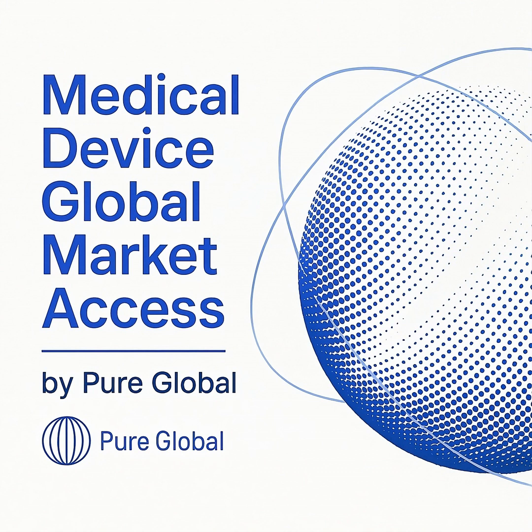For all devices, excluding the very lowest risk Class A non-measuring and non-sterile products, you must apply for an import license using Form MD-14. This application is submitted through the CDSCO's online portal and must be supported by two crucial dossiers: a device master file, or DMF, for each specific device or device family, and a plant master file, or PMF, for each manufacturing site. This is where your existing FDA technical documentation becomes invaluable, as it can be leveraged to build these files.